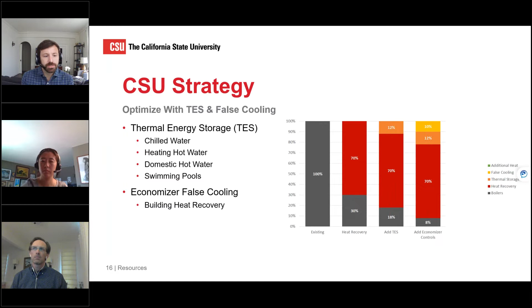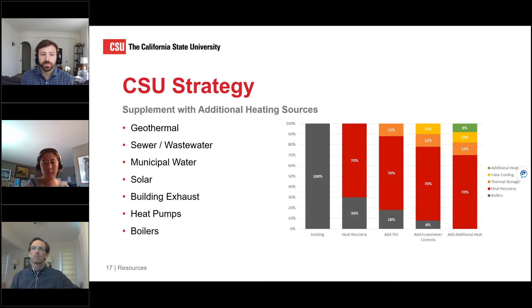And then finally, supplementing with additional heating sources. These are typically more expensive or more challenging, so that's used for those peak design day conditions. And that can comprise either geothermal, sewer wastewater heat recovery, recapturing heat off municipal water, solar, building exhaust, or additional heat pumps and boilers. We're really focusing on what are the most cost-effective and efficient strategies first, how to optimize those, and then look to additional heating sources as a long-term approach to fully decarbonize existing systems.